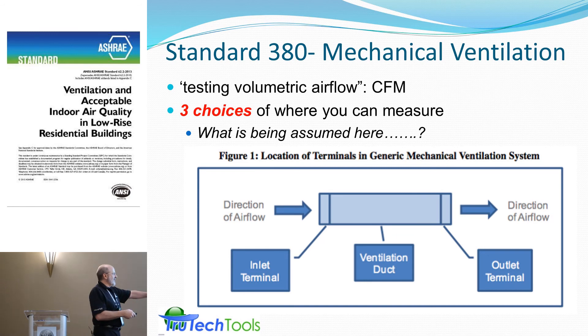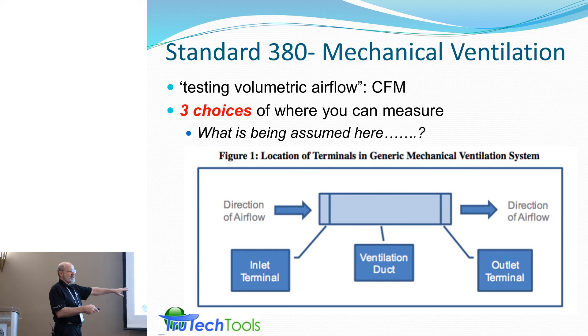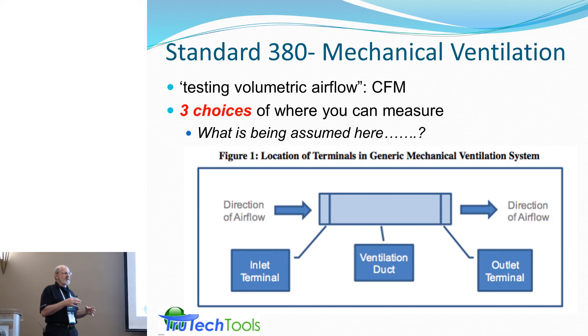If you're saying the inlet CFM equals the one you measure in the duct, equals the one you measure at the outlet — if all three are equal, what's being assumed? No leakage. So no leakage between any of these points. If there's any duct leakage between these points, you may not have equivalent measurements all the way along.